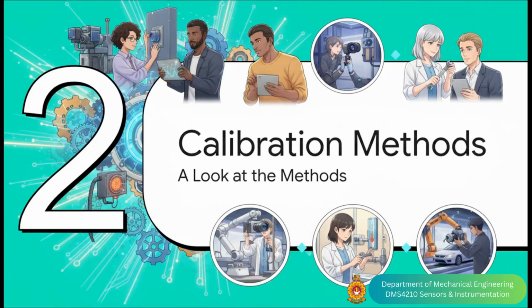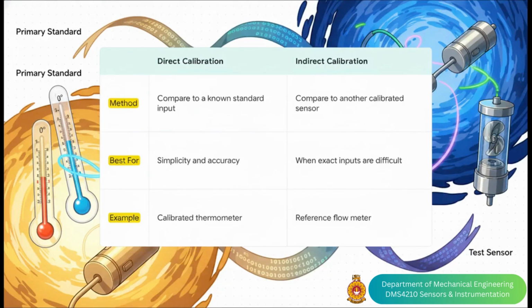Right, but it's not like there's just one way to do this. Calibration isn't a one-size-fits-all kind of deal. Depending on the sensor and what it's being used for, engineers have a few different methods to get the job done right. The two big ones are direct and indirect calibration. Direct is exactly what it sounds like. It's simple, super accurate. You compare your sensor directly to a gold standard reference. Think about checking a new kitchen thermometer against a super precise lab one. Indirect is what you use when creating that perfect input is tough. So instead, you just compare your sensor against another sensor that you already know has been perfectly calibrated.